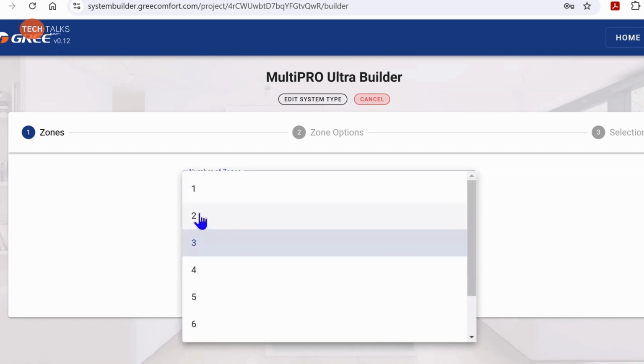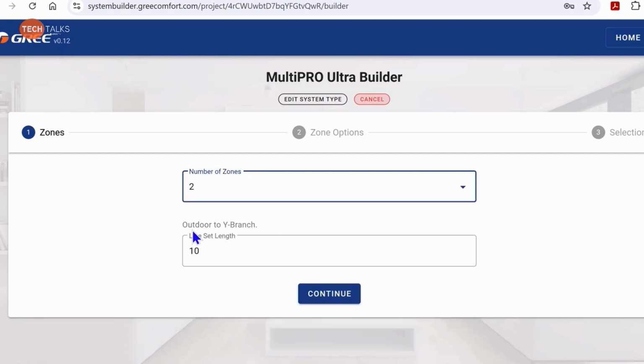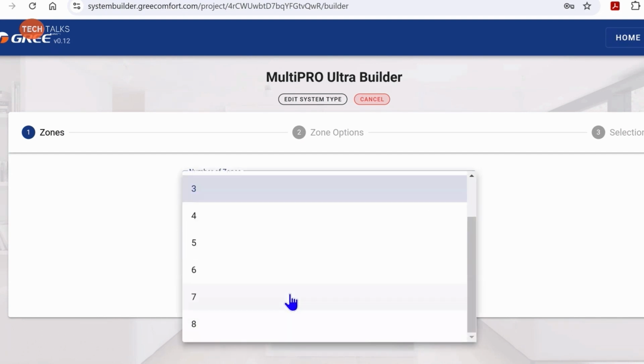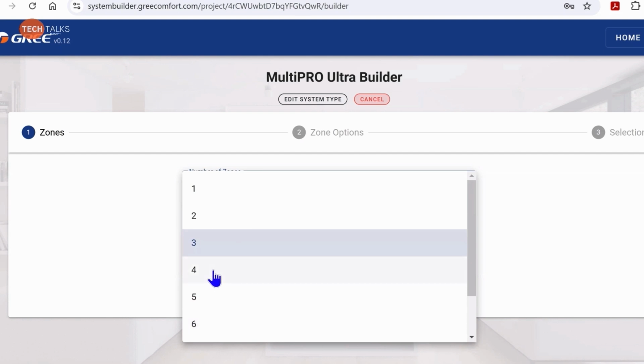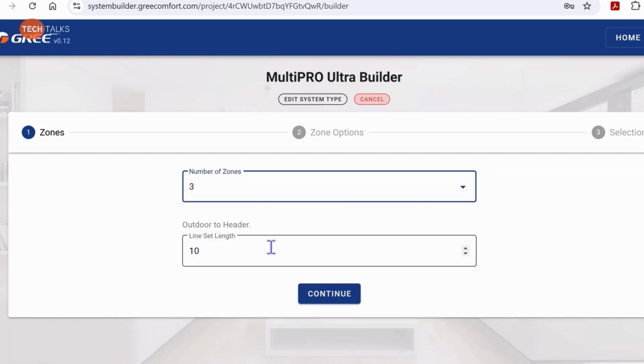If I do 2 indoor units, it's defaulting to a Y branch, okay? So if I only got 2 indoor units, it's going to default to a Y branch. If I'm doing more than 2, it's going to default to a header. If I was doing like 5 or more, it's going to default to the 8-port header. If I'm doing 3 or 4, then it's going to default to the 4-port header. All right, moving on.